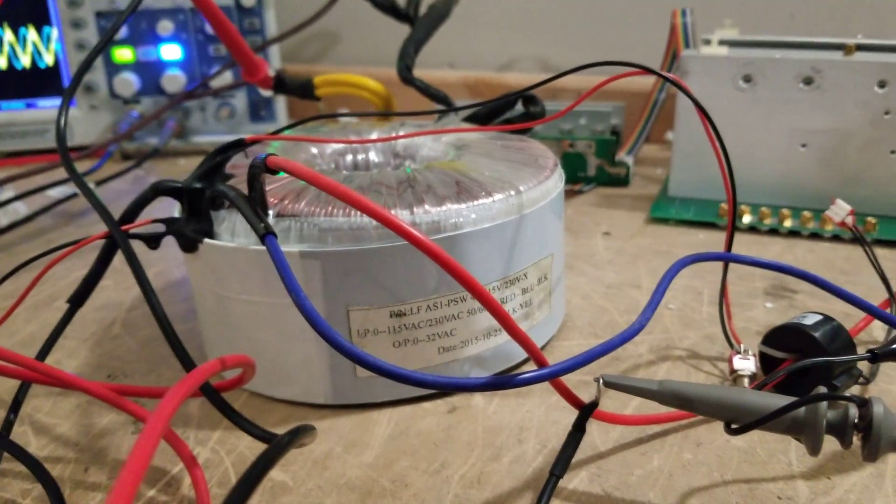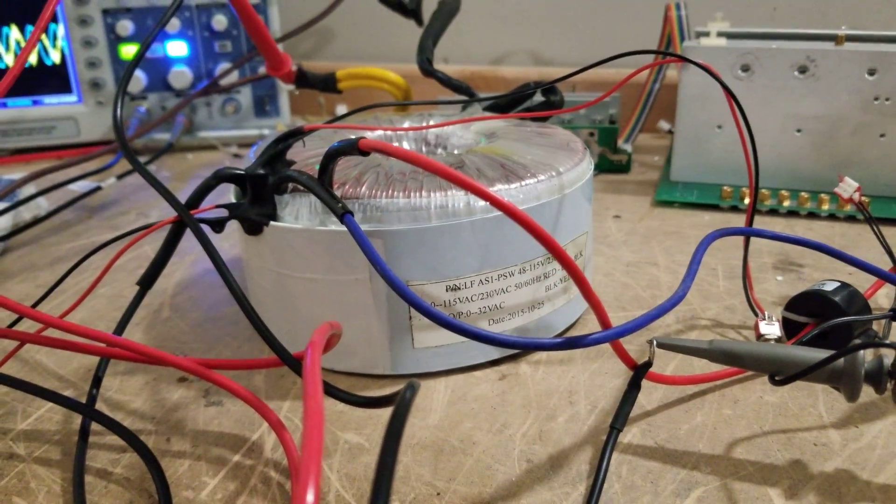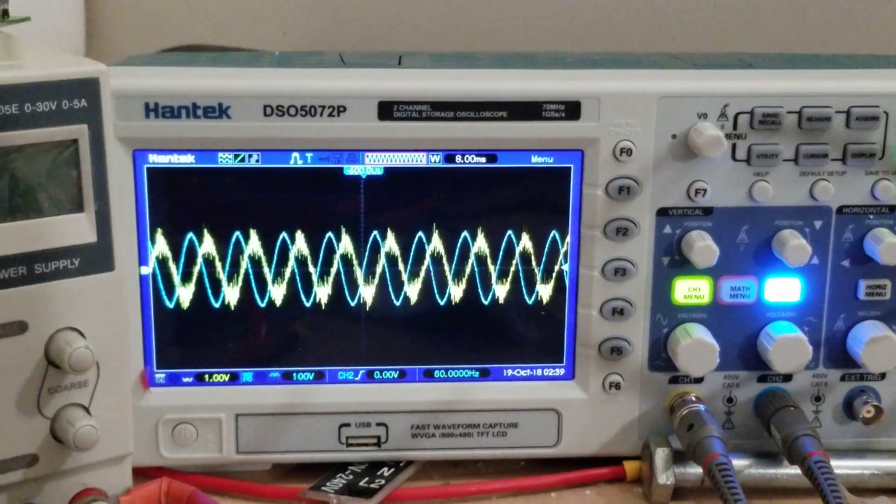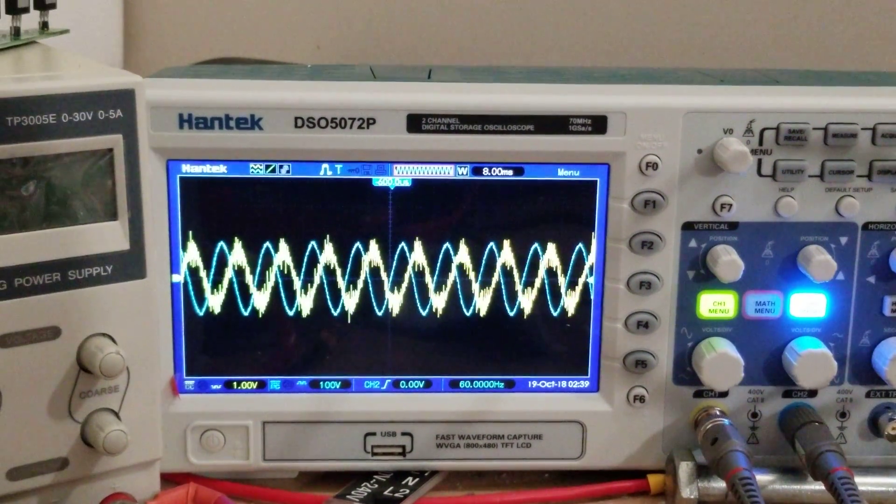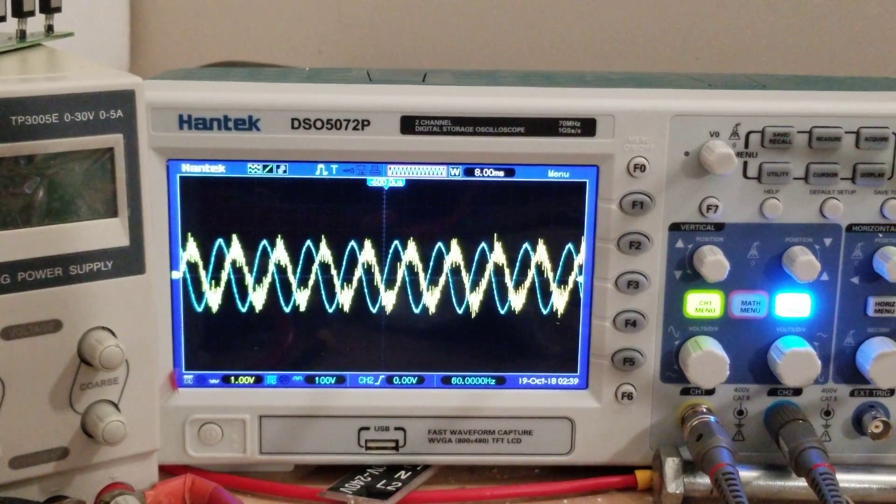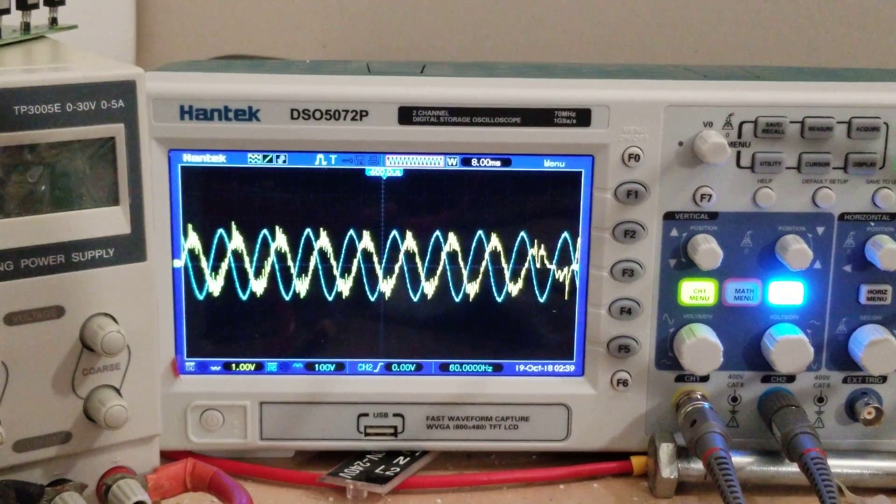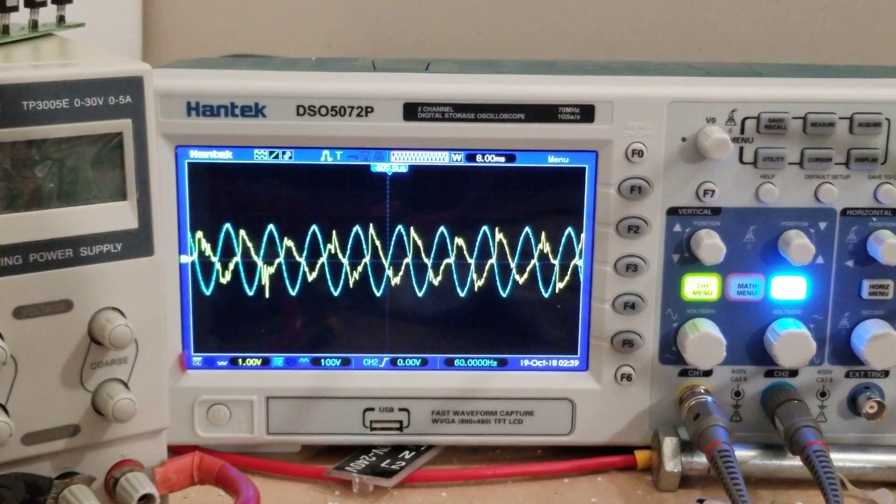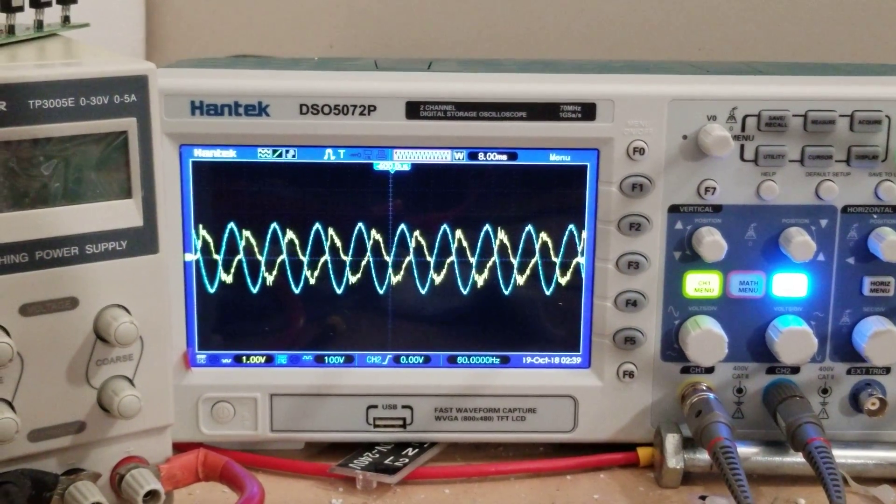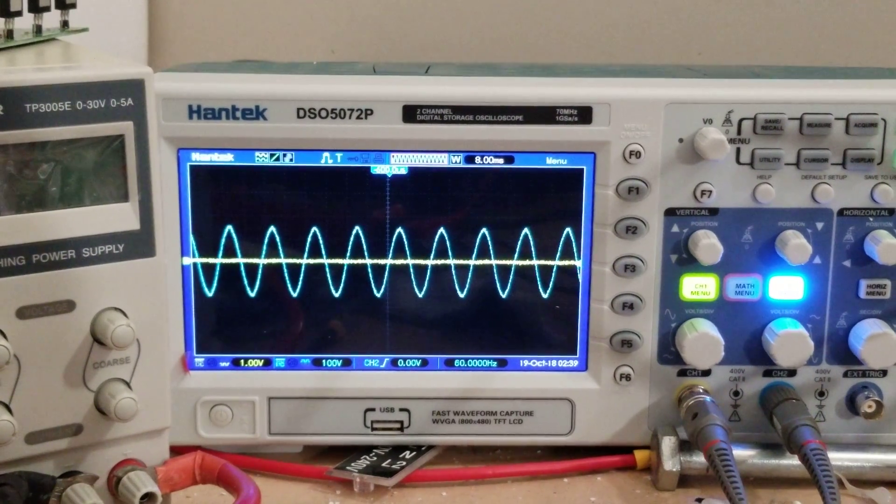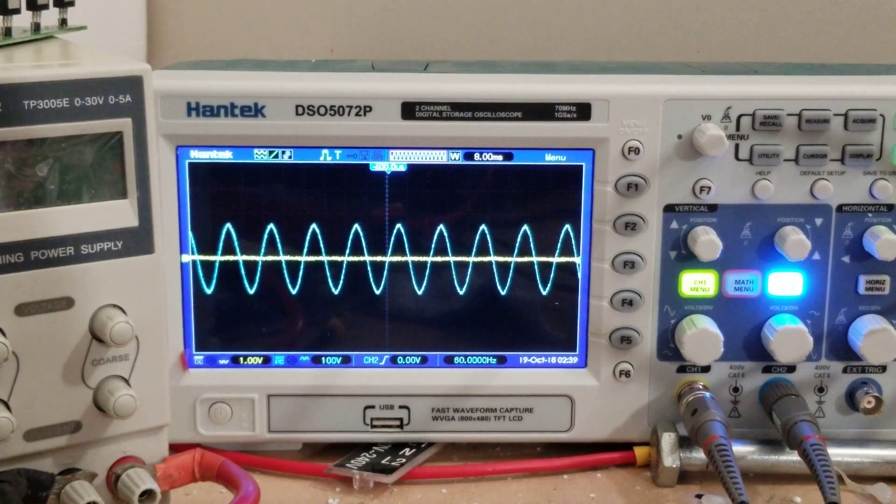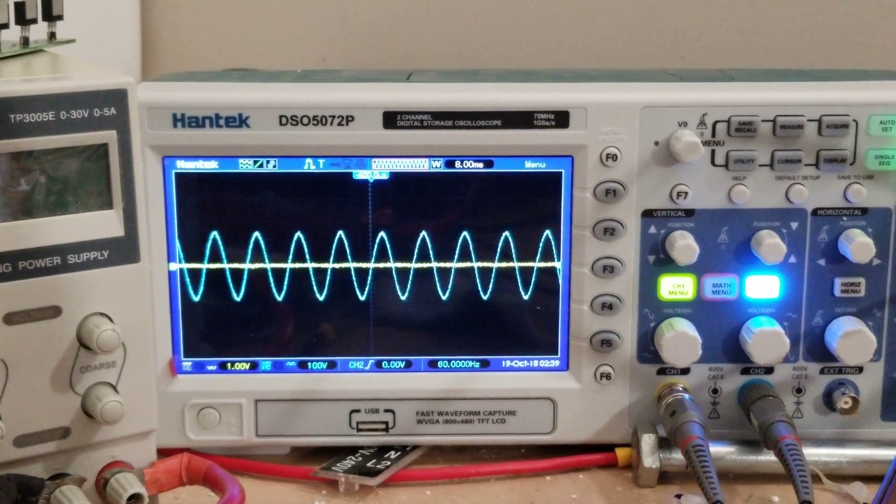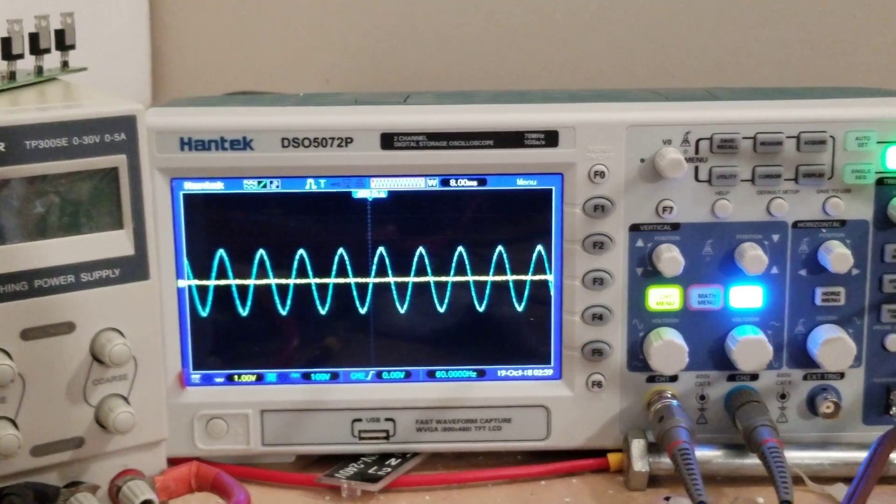This particular transformer has an issue. You can probably see it right there, so it's erratic and there's a lot of noise on it. This was brought to me for repair. You can see how bad it is there. The transformer itself is humming, is even losing, it's like almost a dead short. It's really strange.